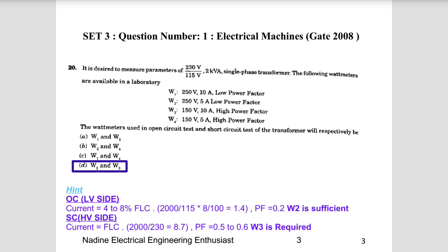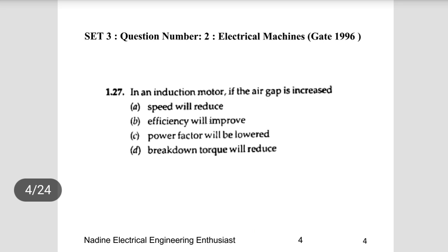To summarize: for the 230V/115V, 2 kVA transformer, we select the correct wattmeters for accuracy. We use a low power factor meter for the open circuit test (power factor ~0.2) and a high power factor meter for the short circuit test (power factor ~0.5 to 0.6). The current in the open circuit test is 4 to 8% of full load current.